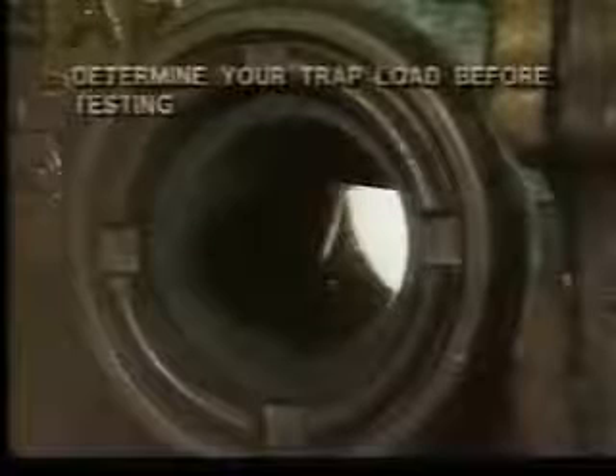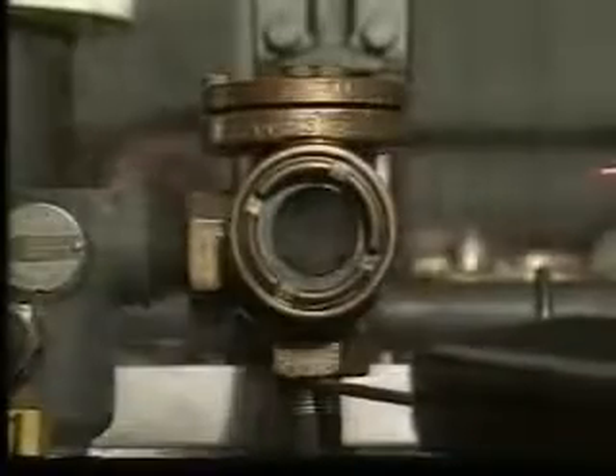You should determine your trap load before testing. Depending on the condensate load, there can be a continuous flow or it can be shut for a considerable length of time. On light loads, such as drips, traces, and radiator trap applications, the noise level should be relatively low. A high volume of sound will indicate a blow-by condition.